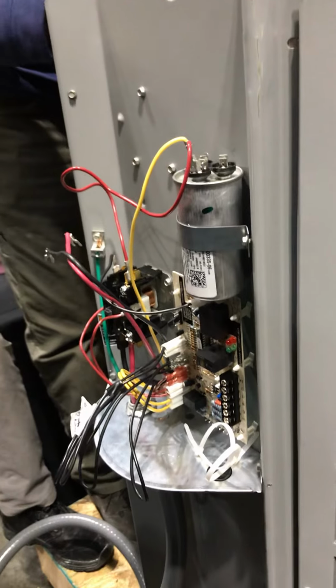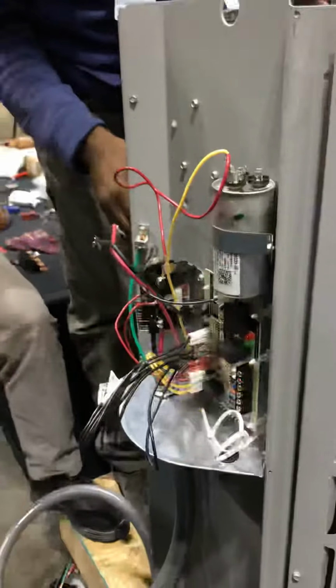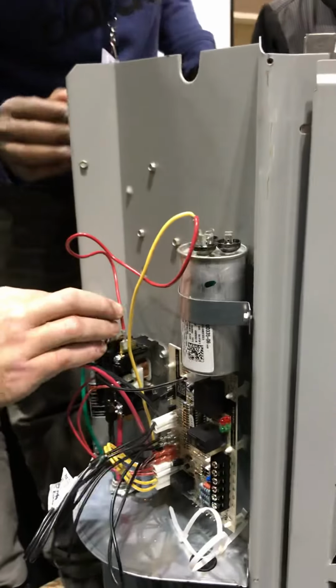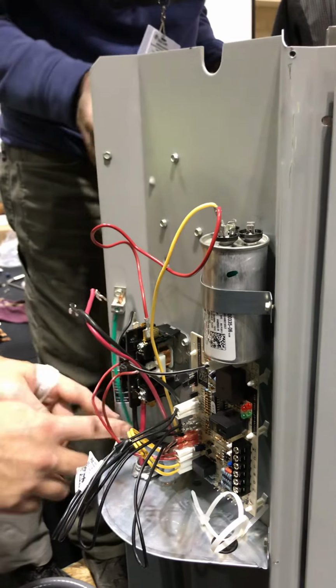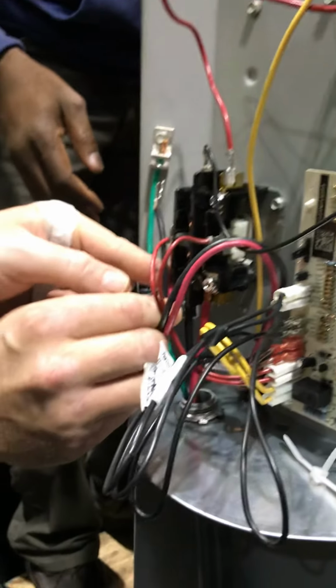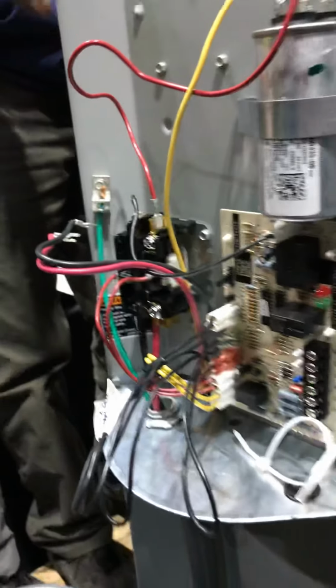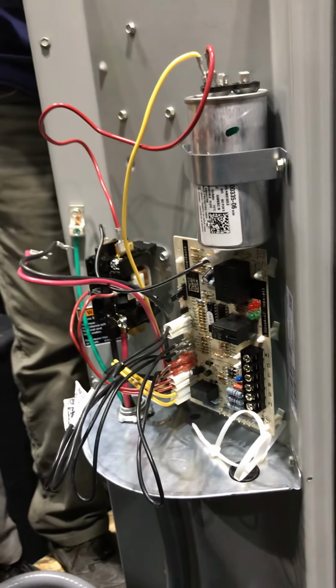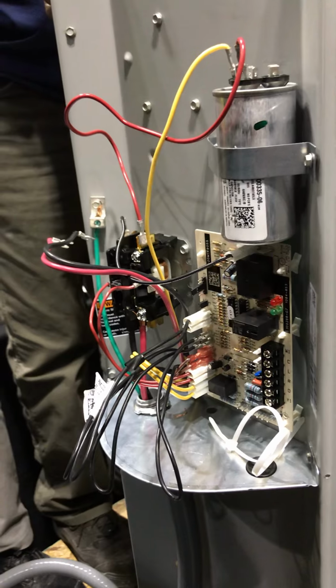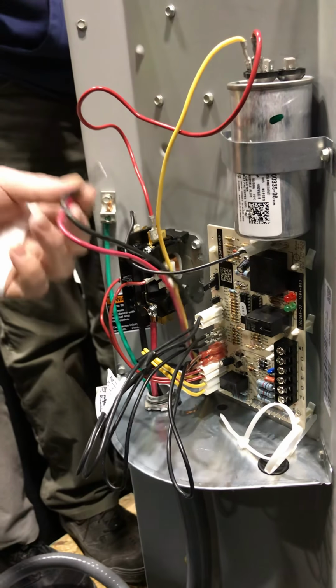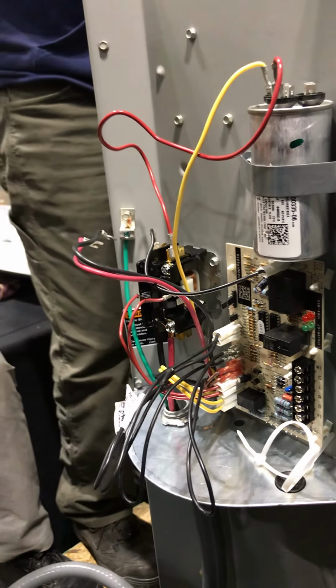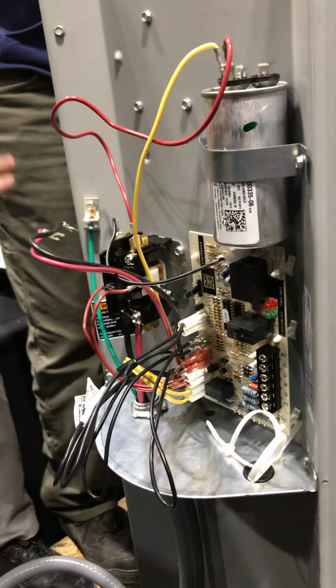It's either shorting out with the ground, like if something was touching my ground, okay? Down here, if this was nicked and touching that, it would trip. Or maybe this wire came over here and started touching this wire, it would trip. But I could see that. That's easy to see. You'll notice that. It'll smell too. You'll smell that burnt plastic. You'll see burnt plastic. But let's say that none of that's happening. Nothing's burnt. You can't tell anything.